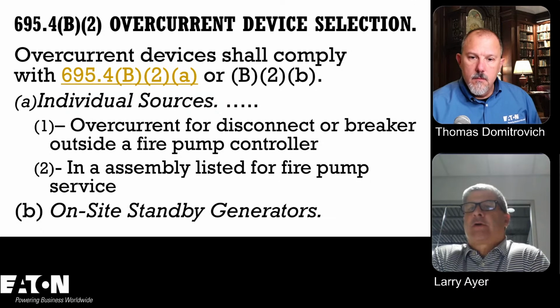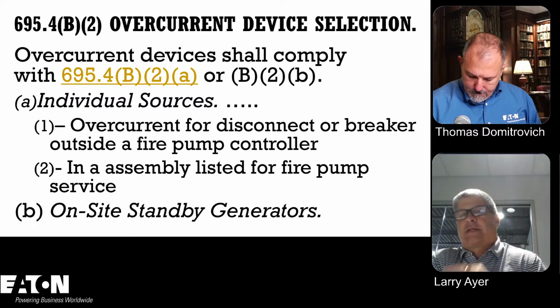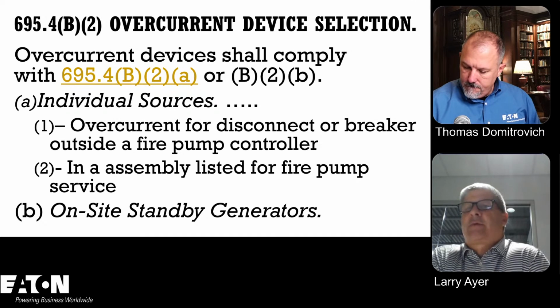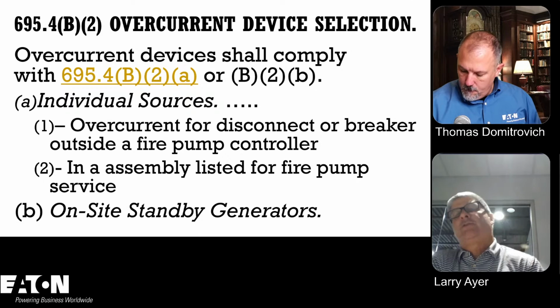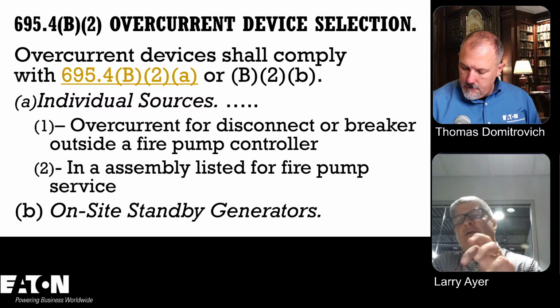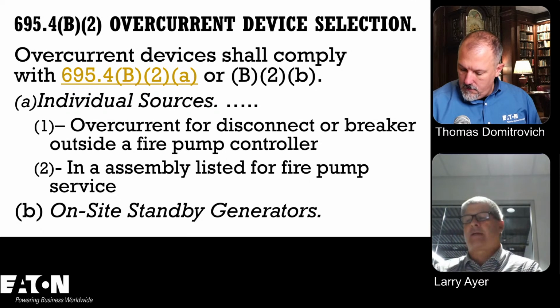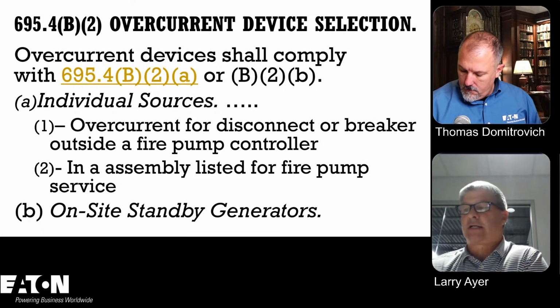So if you have overcurrent for a disconnect or breaker outside a fire pump controller, so those are where you tap off a service and you provide a disconnect ahead of the fire pump controller, that's an individual source. Or if you do a fire pump controller, that's a listed assembly. So you treat these two different ways, and then you also have the on-site standby generator. That's really a third way, and we go into that in more detail in the next couple slides.